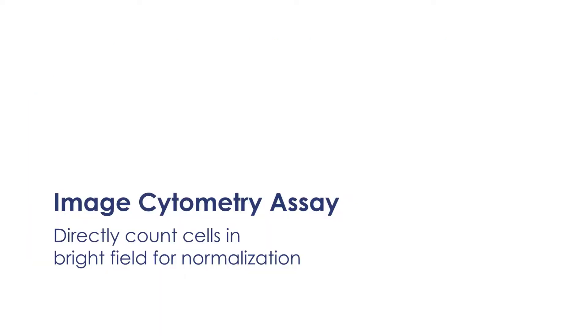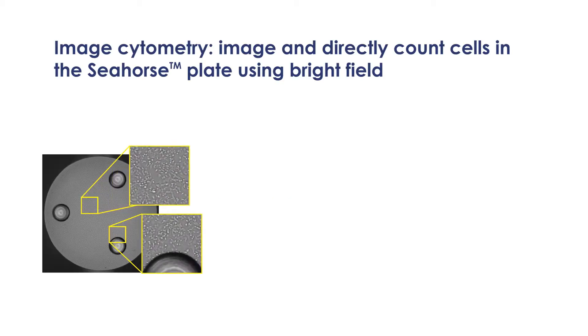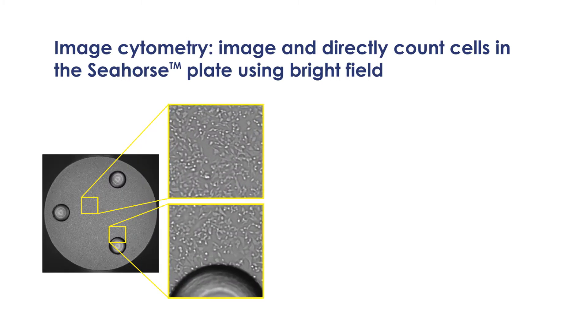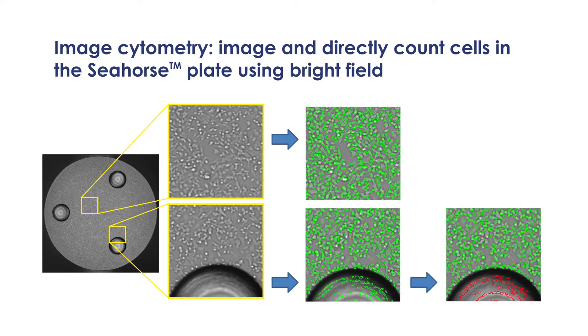In contrast, the image cytometry method images and analyzes acquired images directly from the wells for QC of cell seeding density as well as normalization. High-resolution whole-well brightfield images of the Seahorse XF96 plates are captured. The cells in the wells are then identified and accurately counted by excluding the area of the three posts.